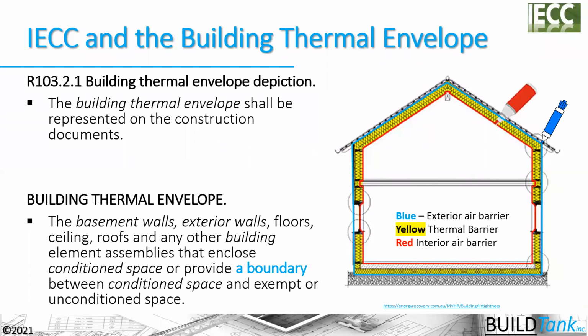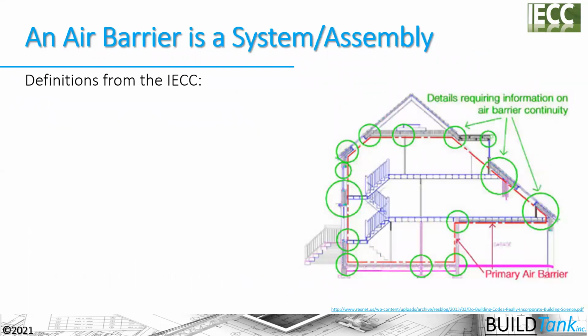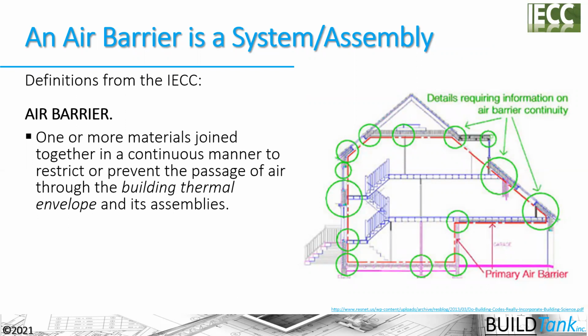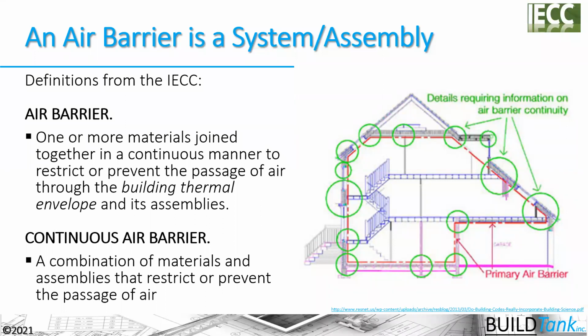What we also know is that the IECC defines the building thermal envelope as these different assemblies that come together to create this boundary condition that ultimately separates conditioned space from unconditioned space. So we have the alignment of our air barrier systems and our thermal barrier systems coming together, again, to give us this clean separation, this clean boundary that separates conditioned space from unconditioned space. And so what is that ultimate boundary? Well, the IECC also defines these things as well. It defines this air barrier system that is this grouping together of different materials and assemblies that are joined together to create this continuous boundary condition between conditioned space and unconditioned space. And the IECC says that we have to have a continuous air barrier, and it defines that continuity of that air barrier in our system.